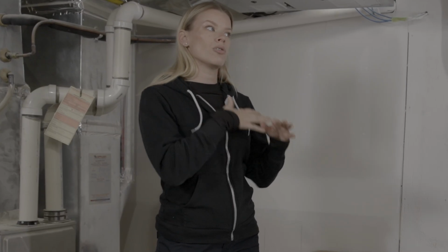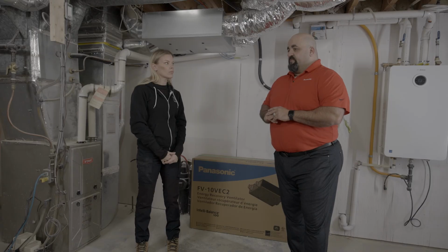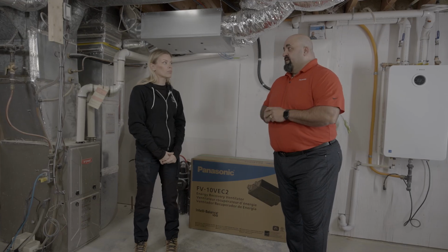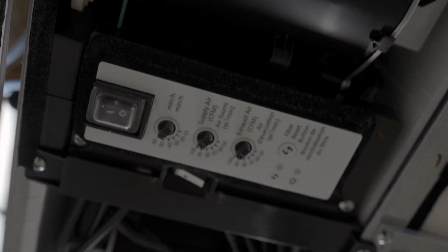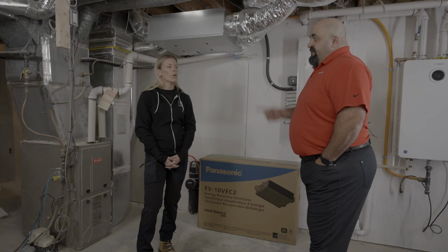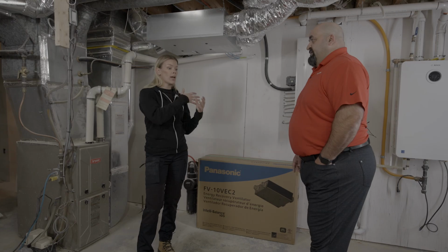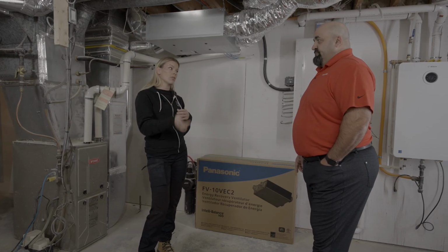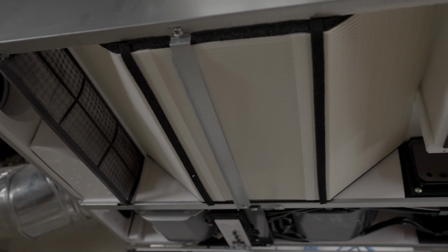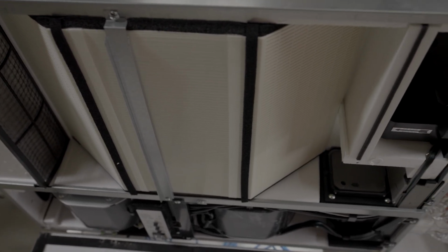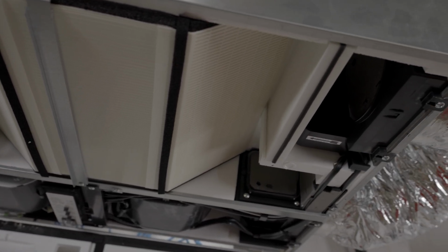How often do you run an ERV, or is that something you should just run consistently? If you're designing a home and an HVAC system, the requirements will be laid out for you in a new construction home. In a retrofit, it's up to you. If you look at the IntelliBalance 100 and the onboard controls, you can put it on for 20 minutes an hour, 40 minutes an hour, or keep it on full continuous run. So it can already be programmed to run a certain amount of time instead of constantly coming down here and setting it. In an environment like this, you probably want to run it more than not, to make sure it's running and doing its job.